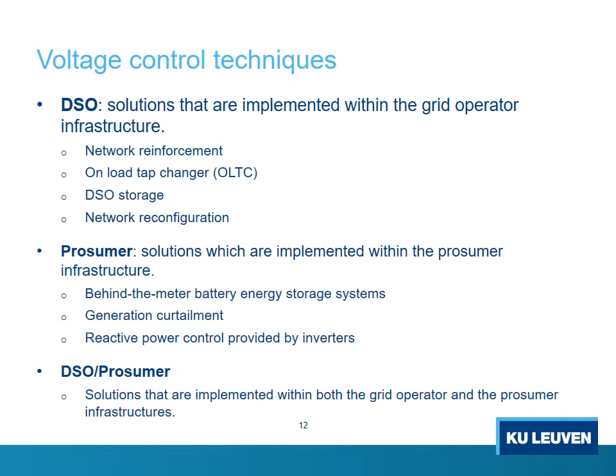The second category: solutions which are implemented within the prosumer infrastructure, such as behind-the-meter battery energy storage systems, curtailing the photovoltaic generation, and reactive power control provided by the inverters. The third category: solutions that are implemented within both the grid operator's infrastructure and the prosumer infrastructure. The thesis focuses on the second category. Mainly, we use the photovoltaic inverters and photovoltaic battery inverters to solve the voltage problems.